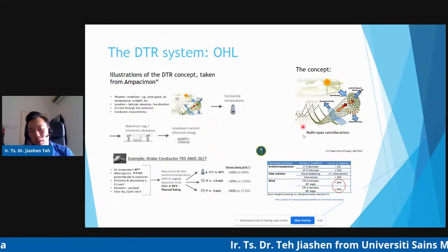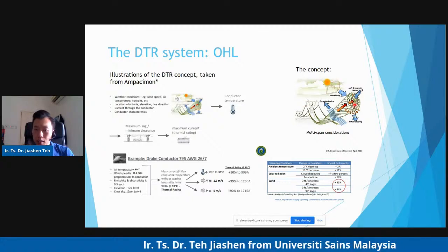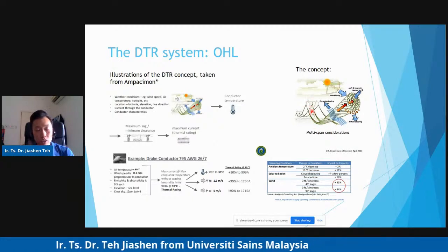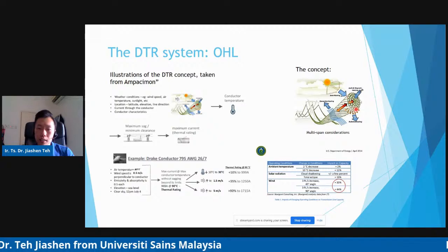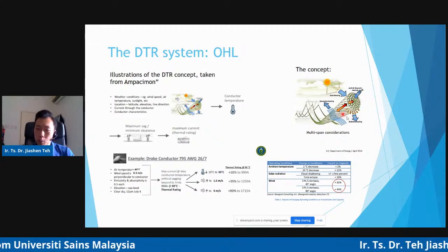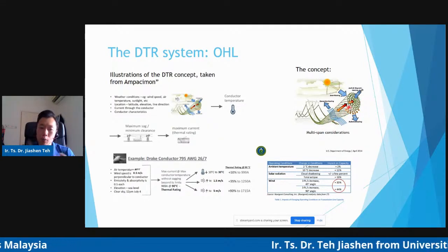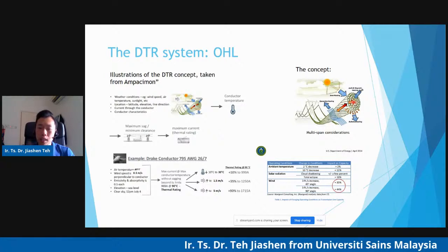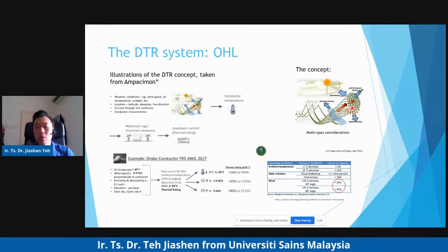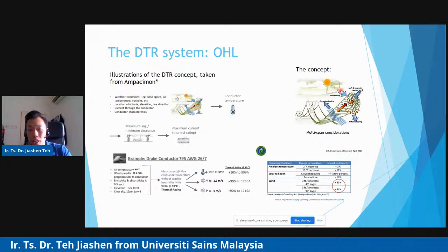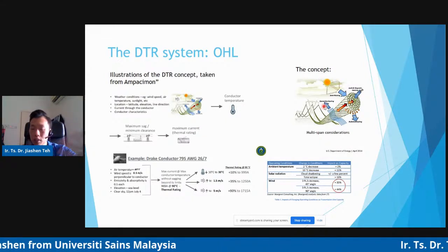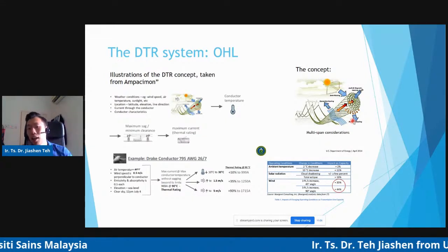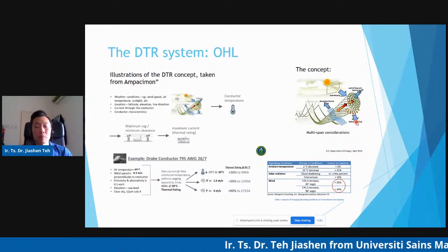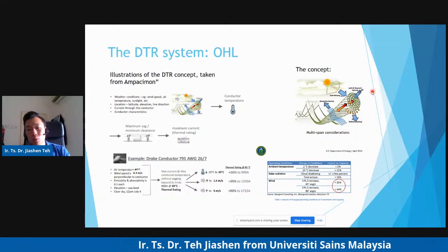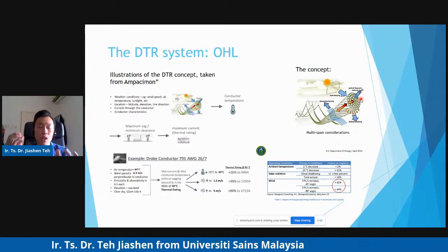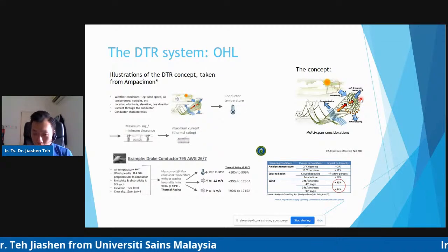This is a particular conductor connected on the transmission tower, and this is a zoomed-in conductor profile, the ACSR, aluminum conductor steel reinforced, conductor of the OHL. It is subjected to solar radiation, convective cooling by wind, and radiative cooling, where heat radiates out, and also heating due to current flowing, since current can create heat as well.